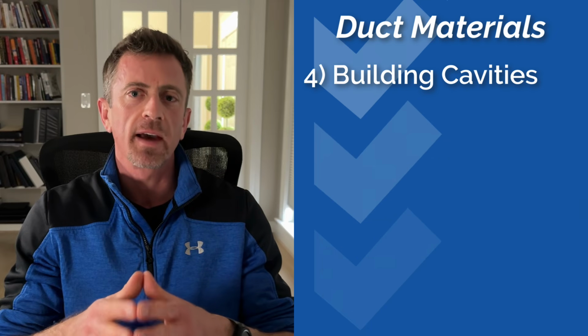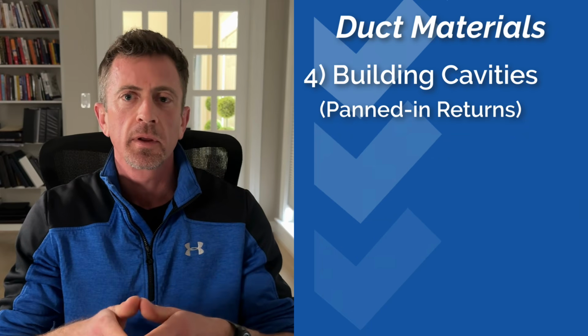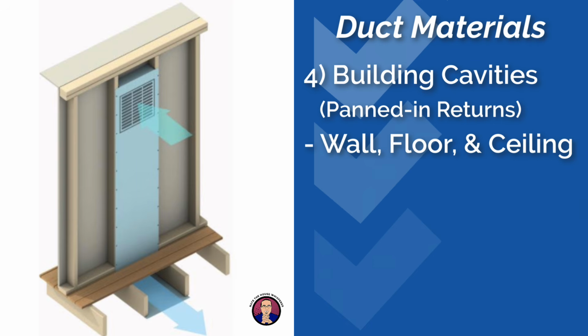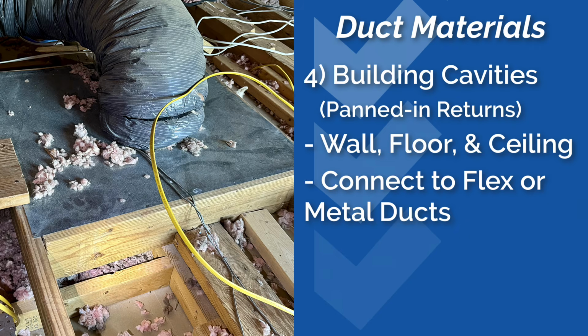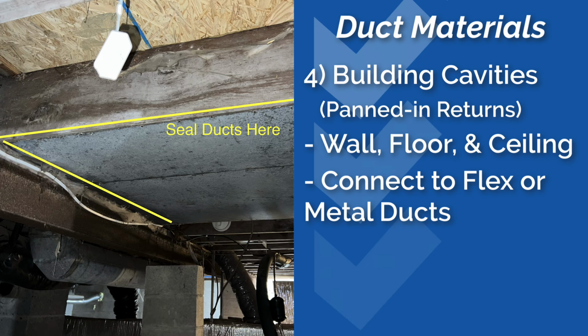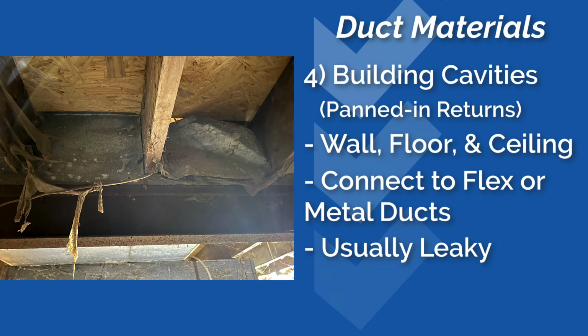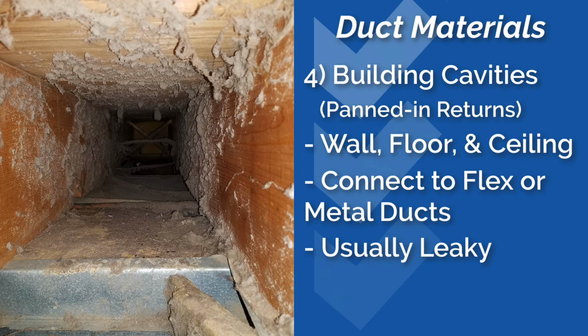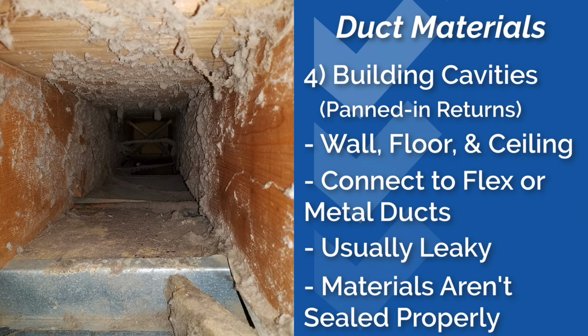Next up are building cavities or panned-in returns. These are wall, floor, or even ceiling cavities that are used as part of the return side ductwork and are connected to either flex ducts or sheet metal to move air through the rest of the duct system. Usually panned-in returns are one of the leakiest parts of the duct system that use them because they typically rely on drywall, thermopan, or sheet metal to enclose the building cavities, and those materials are rarely sealed properly together. I'll discuss these issues in more detail shortly as well.